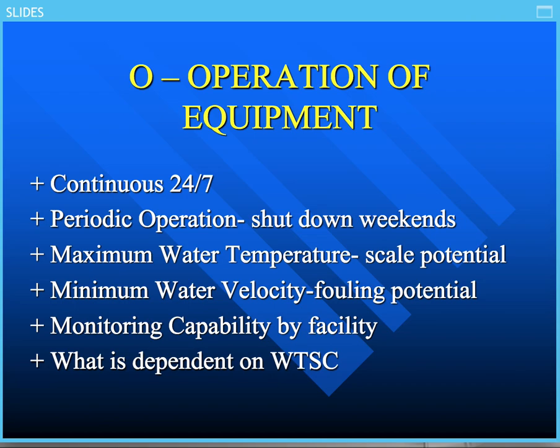Another area we have to look at is the scaling tendency of the water. What is the operation here in regard to the maximum water temperatures? That is because we're looking for potential scale. If that scale comes out on a major heat exchanger, that's a real serious problem. So you have to address the scaling inhibitors you're using to make sure they're compatible, not only with the other inhibitors, but also that they address the type of scale that occurs. Calcium carbonate is the most common one, but if you're using a phosphate treatment program, then you have calcium phosphate. It has to be controlled. So scale is a very important criterion for a first-rate cooling water program, and it addresses the maximum water temperature.